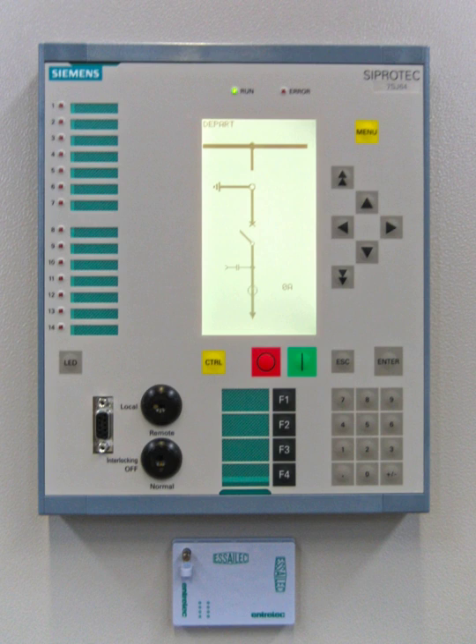Protection coordination is also handled through dividing the power system into protective zones. If a fault were to occur in a given zone, necessary actions will be executed to isolate that zone from the entire system. Zone definitions account for generators, buses, transformers, transmission and distribution lines, and motors. Additionally, zones possess the following features: zones overlap. Overlap regions denote circuit breakers, and all circuit breakers in a given zone with a fault will open in order to isolate the fault. Overlapped regions are created by two sets of instrument transformers and relays for each circuit breaker.